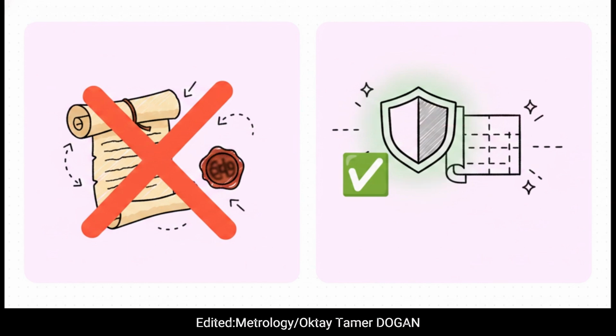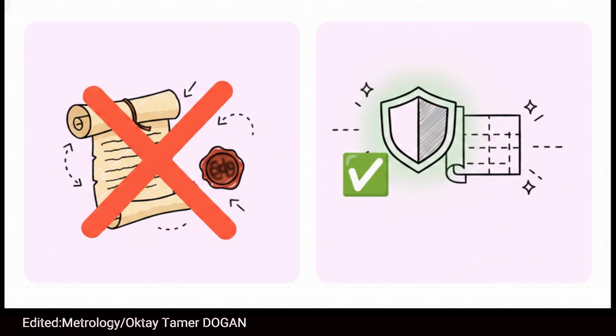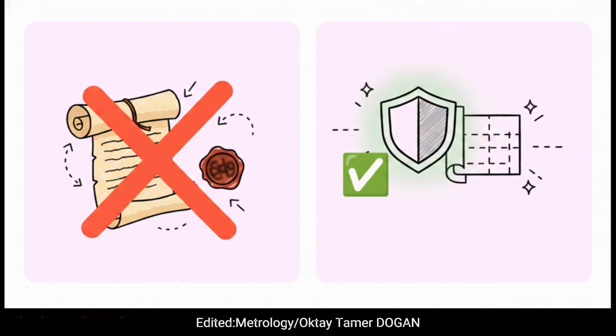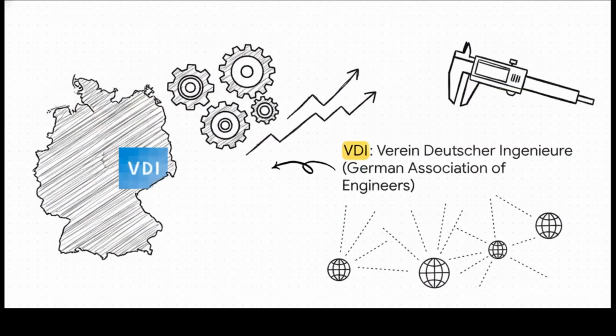Basically, EMP is the maximum permissible error. That's your hard limit before a tool officially fails. SMP is the shift, maximum permissible error, which accounts for acceptable deviation when you're using different parts of the scale. It was a monumental shift, and it forced everyone to totally revise how they declare compliance. But to figure out the actual physical methods we need to hit those new ISO targets on the workbench, we still have to look to Germany.